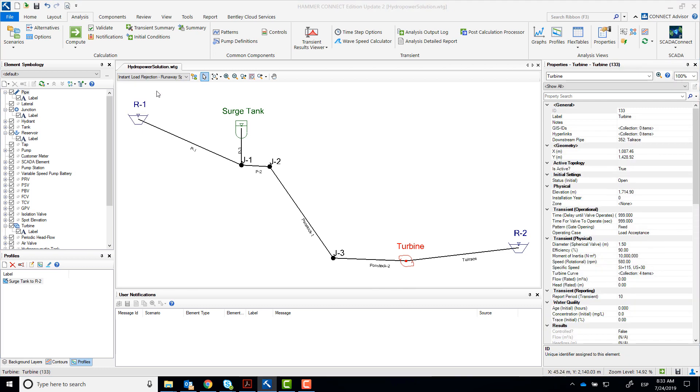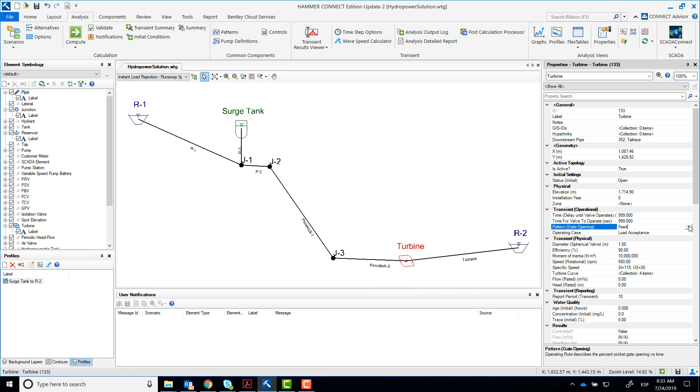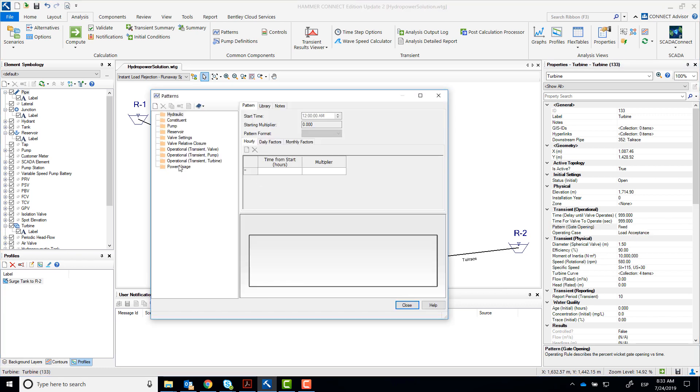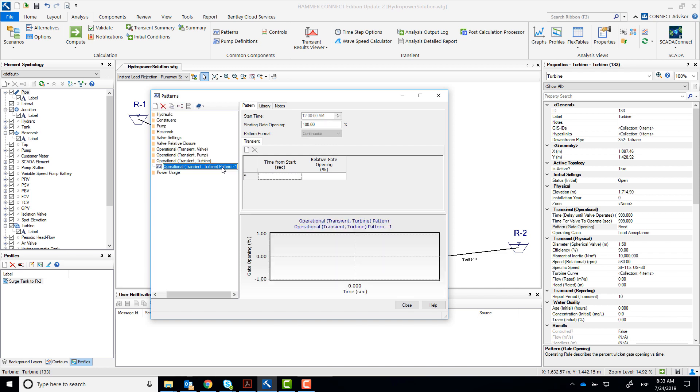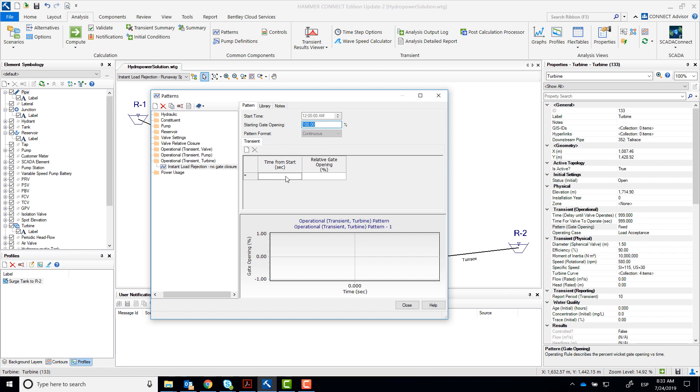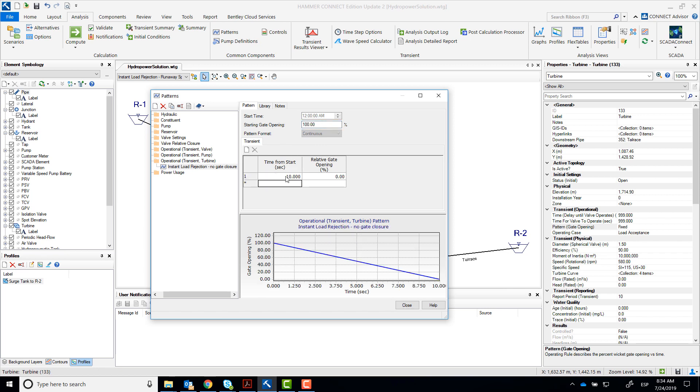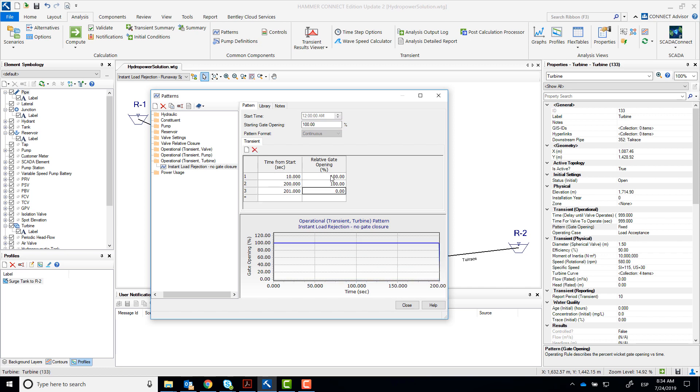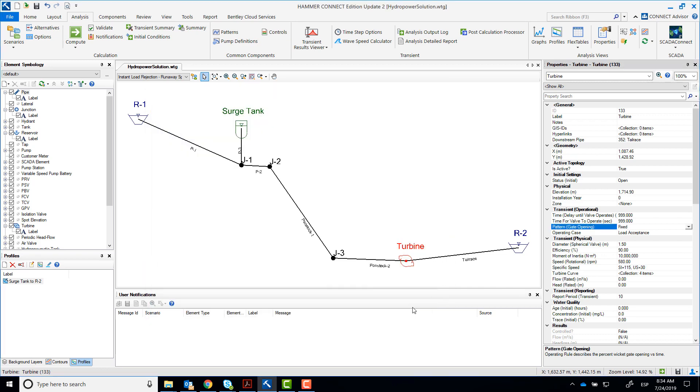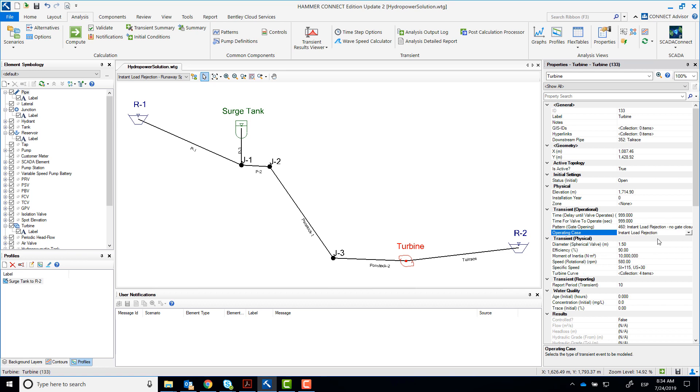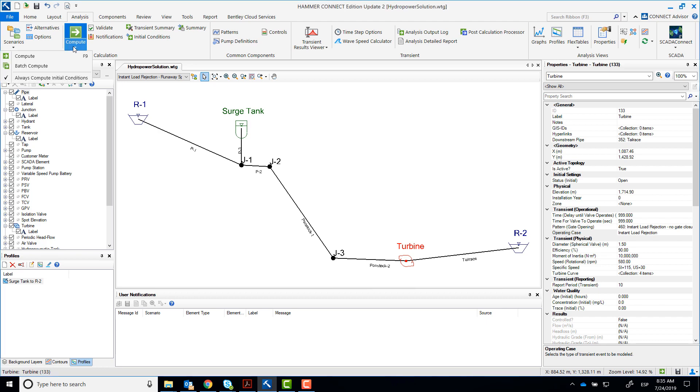Select runaway speed as your current scenario. Double click on the turbine and enter the operational pattern that you'll use for this scenario. Create a new pattern. The wicket gate will start 100% open and will close at 200 seconds. Remember the simulation only lasts 150 seconds, so the gate will be open all the time. Select that new pattern and set the operating case to instant load rejection.